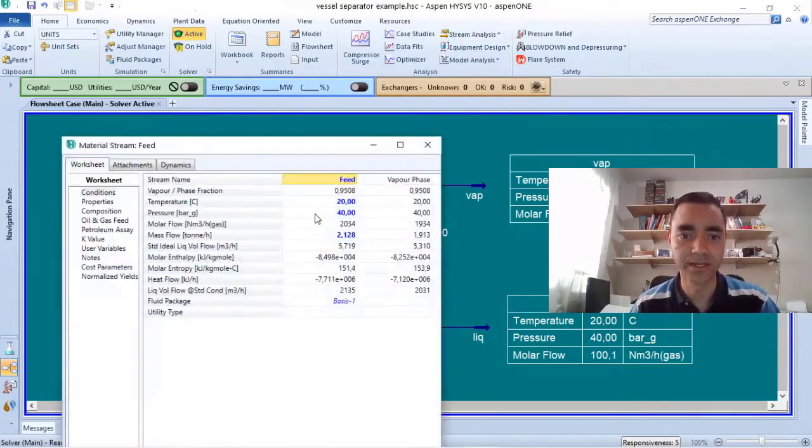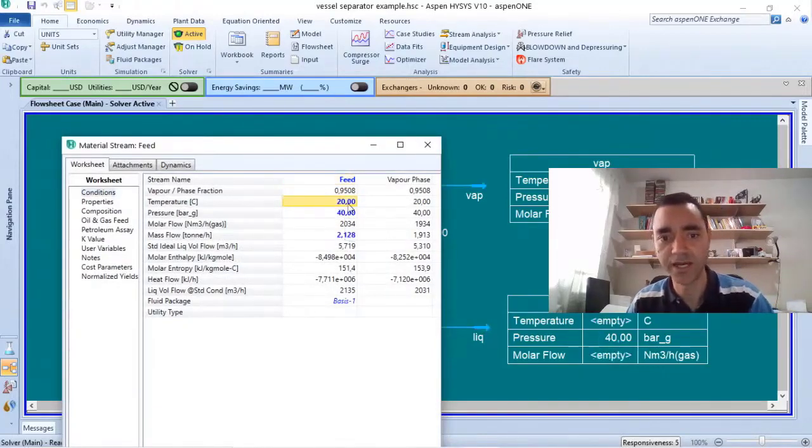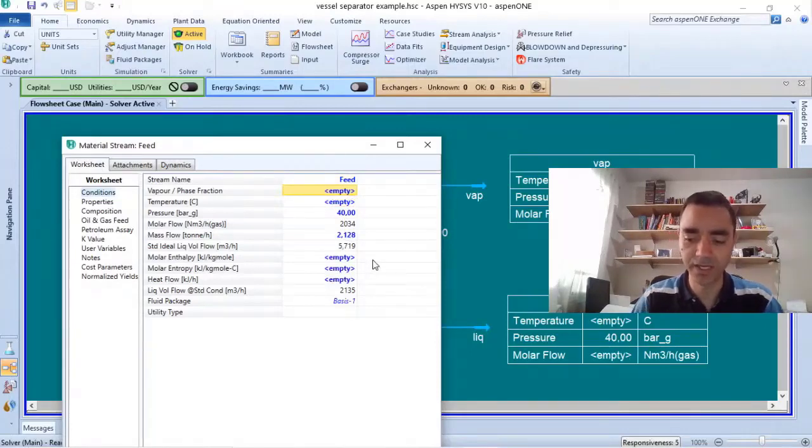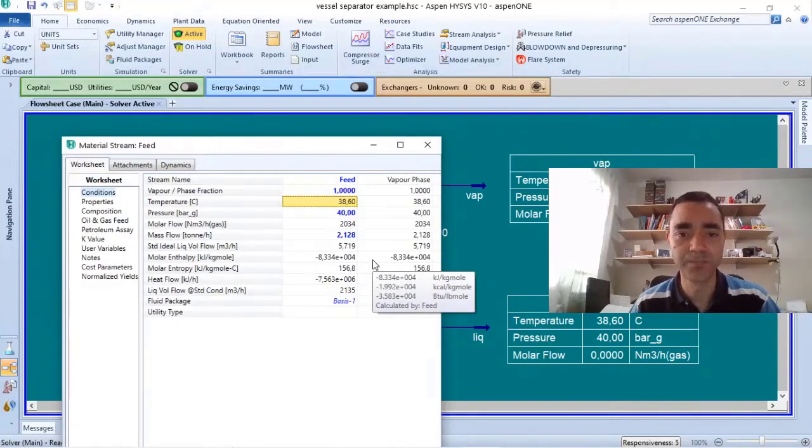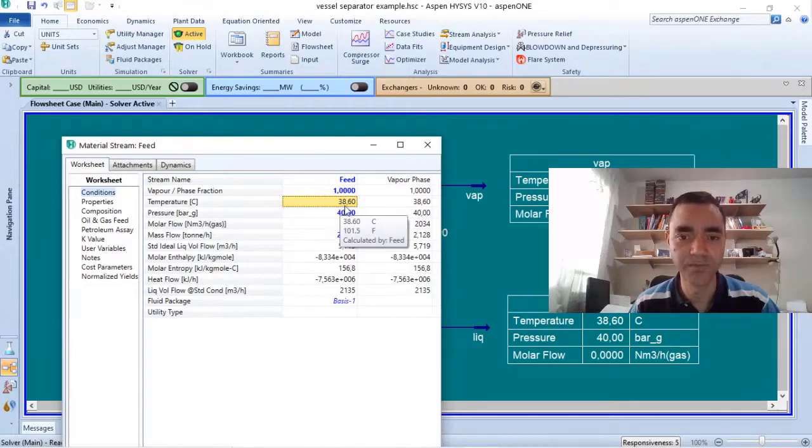You can answer this question in many ways. One way is to delete the temperature and consider that my stream is 100% vapor. In this case, it is a saturated condition. Any drop in the temperature will lead to partial condensation of the stream. So the minimum condition for not having condensate in my stream is 38.6 Celsius degrees.